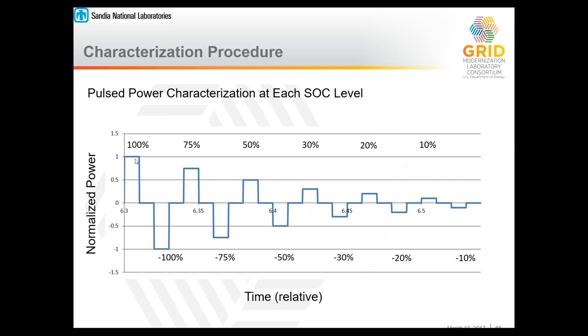What these pulse tests look like are a discharge pulse, followed by a short rest, followed by a charge pulse, followed by a short rest, and then another discharge pulse at steadily decreasing power levels. Now, we've chosen 100, 75, 50, 30, 20, and 10 specifically to match up with the efficiency characterization that Sudeep Dupla presented in his slide on inverter efficiency parameterization.